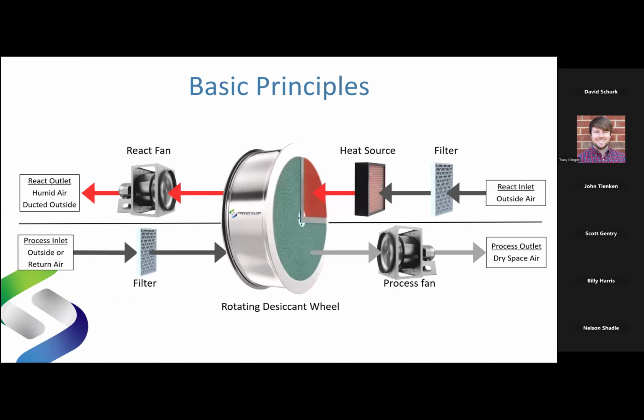All right, here we go. Typical solid desiccant dehumidification system, if you will. It looks weird, you know. It just seems weird. And while it may seem weird, again, as I mentioned, it's thermodynamically eloquent, incredibly efficient, and sustainable done right. Let's talk about it. Also looks a little bit like an energy recovery unit, doesn't it? You got a wheel, you got two air streams, you got stuff going on. It is not an energy recovery unit at all, okay? Big difference. And I'll talk about what some of those differences are as we move forward, but I want to make sure you understand it's not an energy recovery unit. It is an industrial grade commercial desiccant dehumidification system.